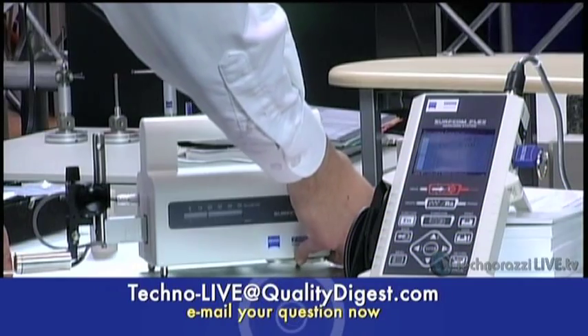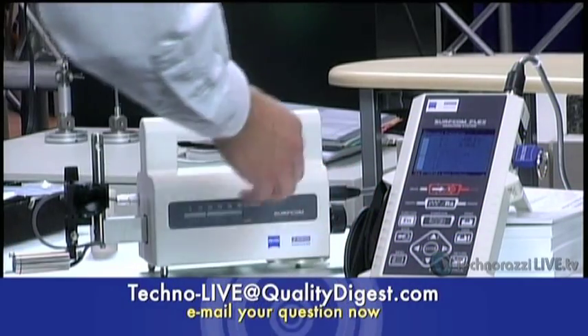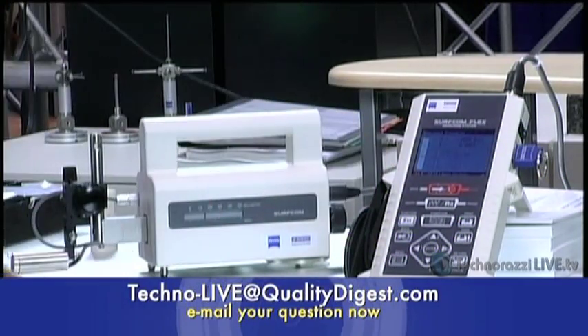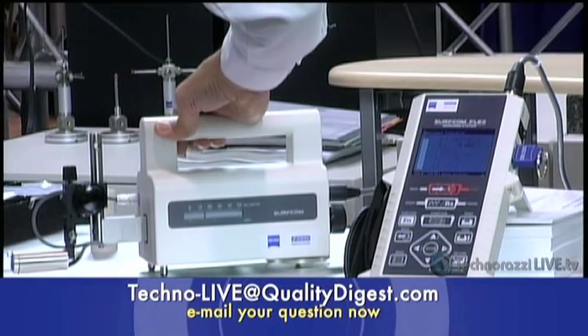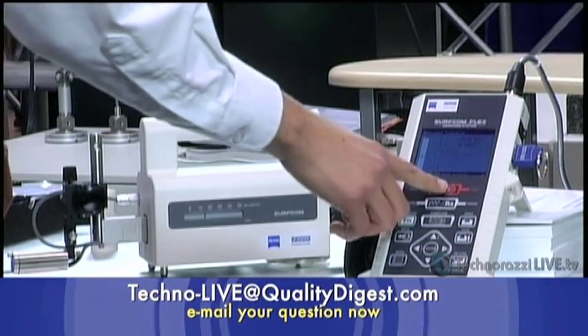And actually, while it's running this time, tell us a little bit about the accuracy. Oh, it's great that you ask about the accuracy of the machine, because when we talk surface roughness, we're not really talking about accuracy. When we talk about accuracy and surface roughness, we're talking about the tracer, the driver. So we want that tracer to be straight to some degree, right? Okay. So the straightness of this specific driver is 0.3 micron in that 50 millimeter measuring range.